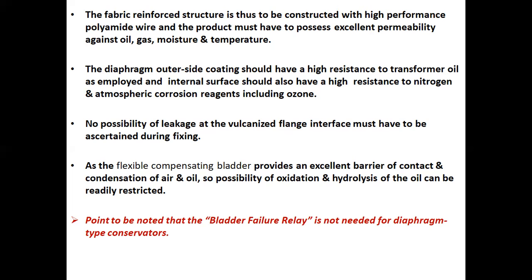No possibility of leakage at the vulcanized flange interface must be ascertained during fixing. As the flexible compensating bladder provides an excellent barrier of contact and condensation of air and oil, the possibility of oxidation and hydrolysis of the oil can be readily restricted.